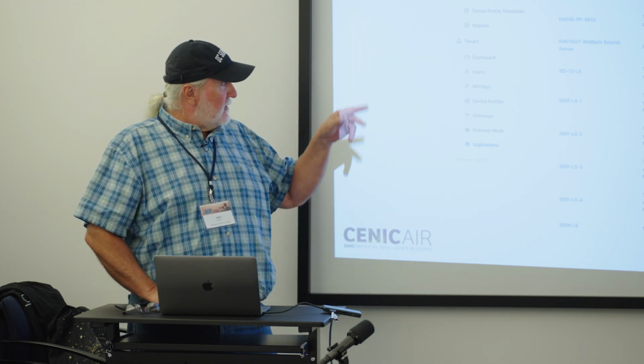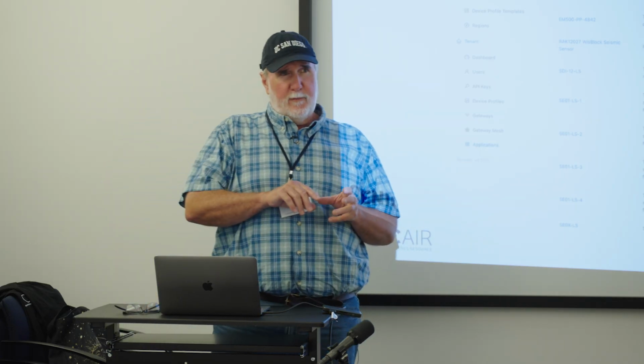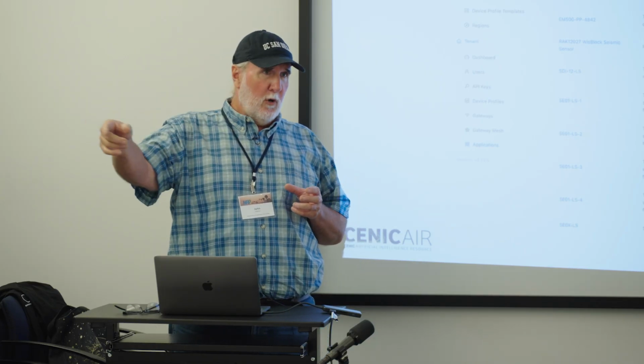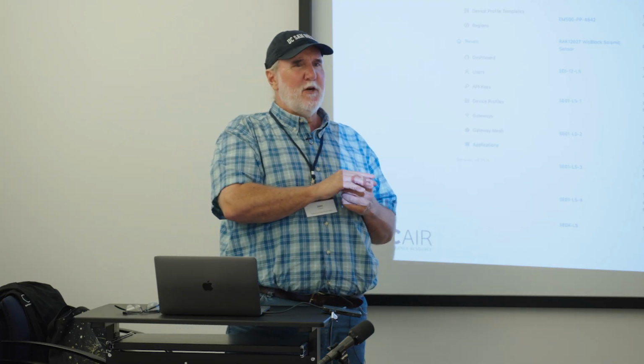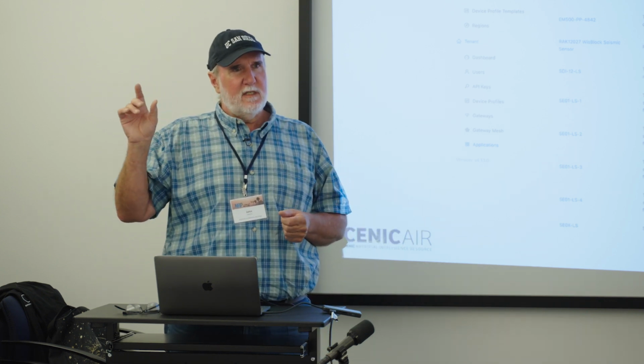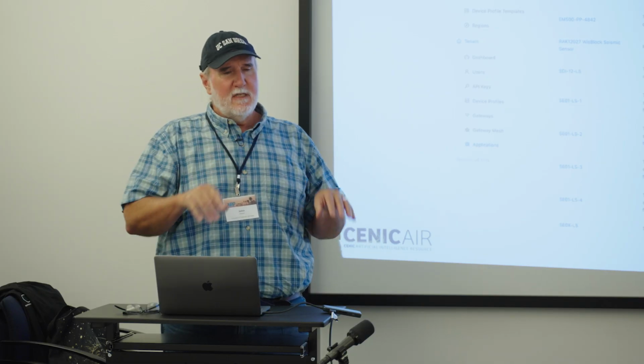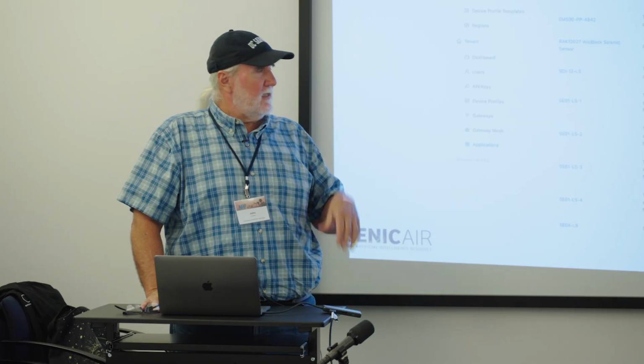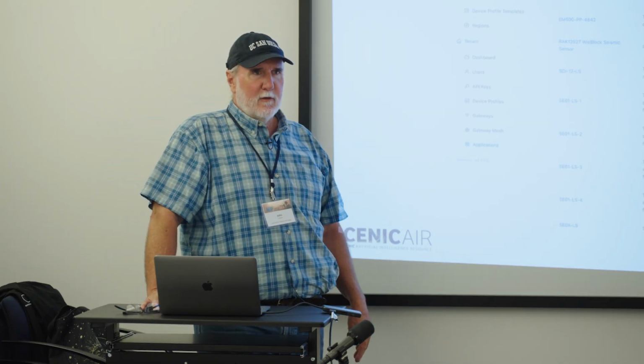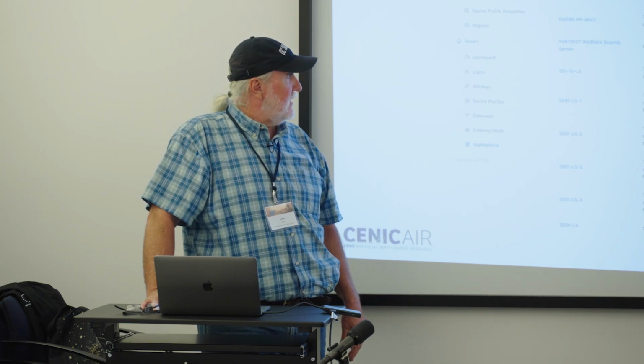So Dragino has this SDI-12 LS, which is solar powered. It's an SDI-12 to LoRaWAN converter box. What we do is figure out how to program the SDI-12 box to send commands to the probe to grab the data. It's really ugly hex coding - you have to figure out from the manuals what code to send to make it send data once every 10 minutes or whatever interval you want. Then you have to parse it, and there's all kinds of evil things you have to do. I should link a spreadsheet before I publish this, but there are some things I've learned through brute force to make these SDI-12 sensors work.